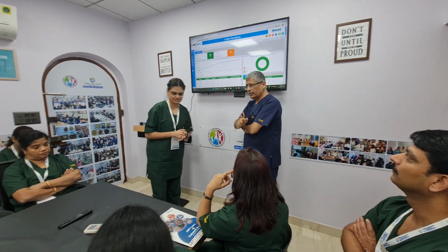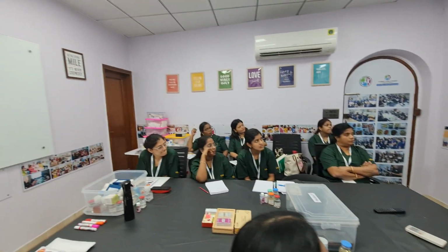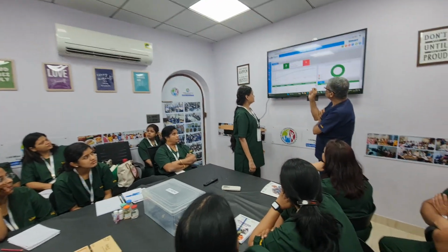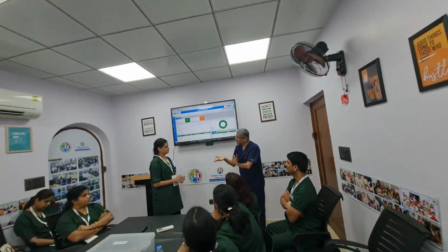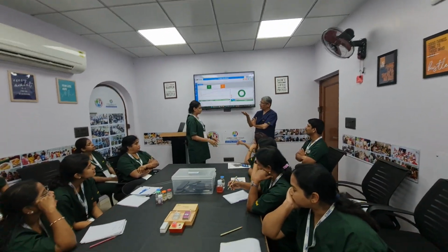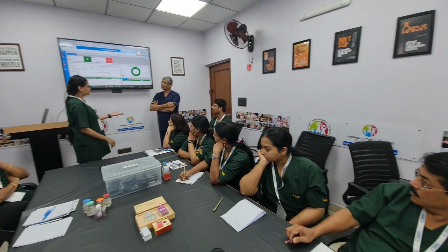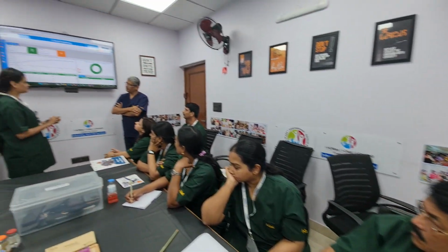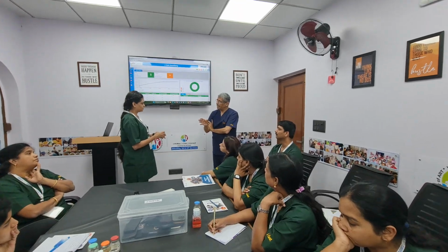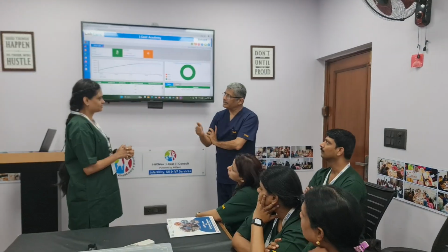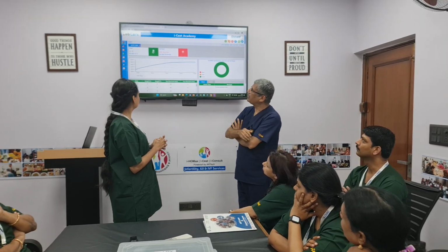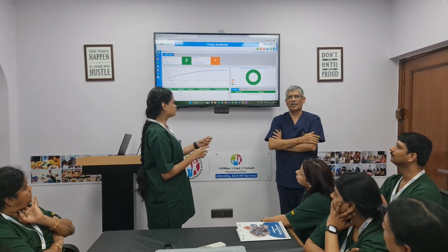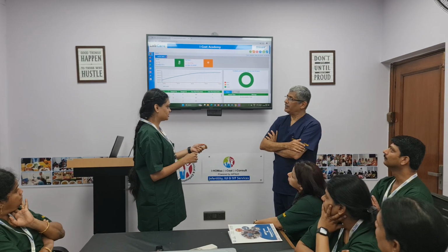So all of you have to know that we are normally working at the normal set flow, which is 19 to 20 ml per minute. And when you open the chamber, what happens? It will increase because of the outside. It increases to purge very rapidly to get the gases inside. And why hasn't the temperature fallen here? It was a very short time.